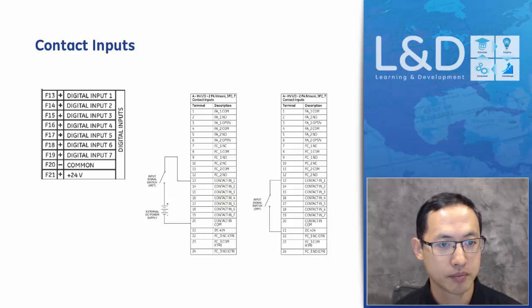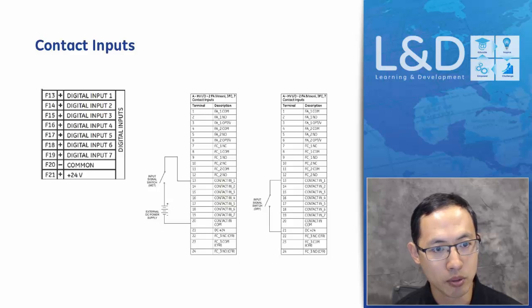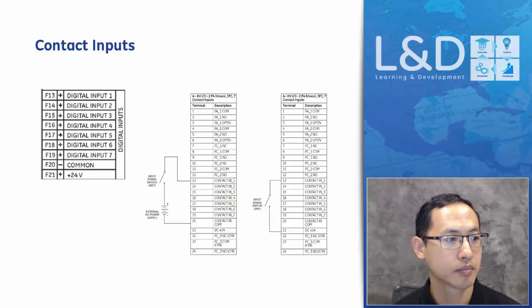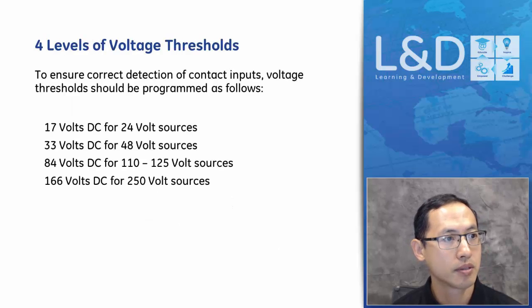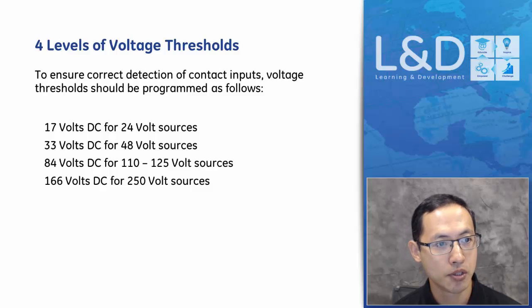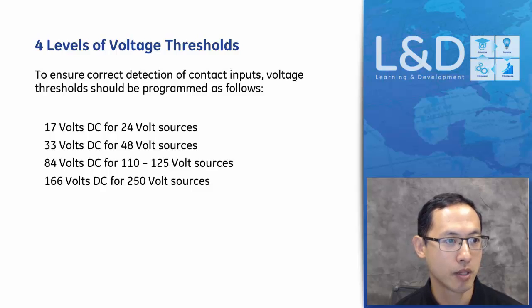But if you want to use the dry mode, then the relay's internal 24 volts DC can be used. So in that case, terminal 21 will be used as a common. There are 4 levels of voltage threshold to use for the different voltage sources of the substation. Because of the interference in substations, we have to set the threshold close to the operating voltage level of the DC batteries. In that case, we can avoid noise induced in the DC system causing maloperation of the contact input triggering.